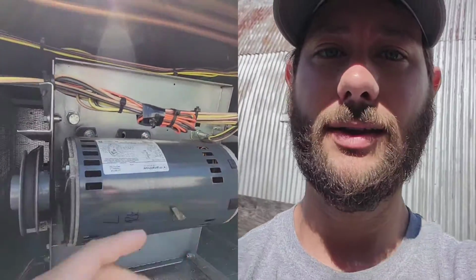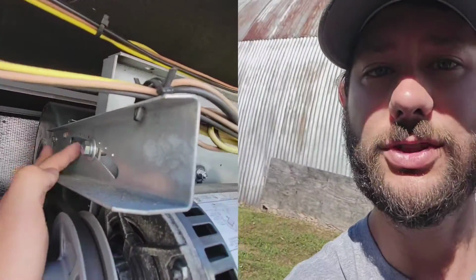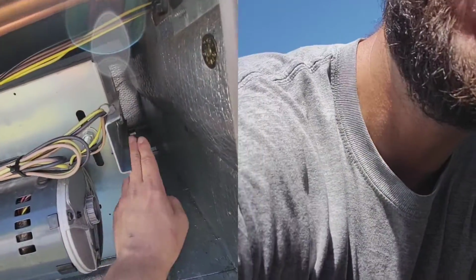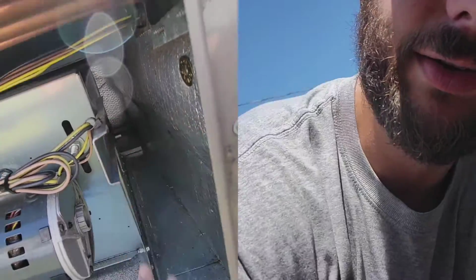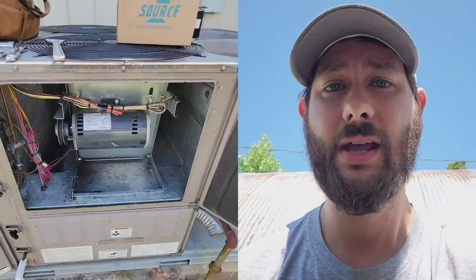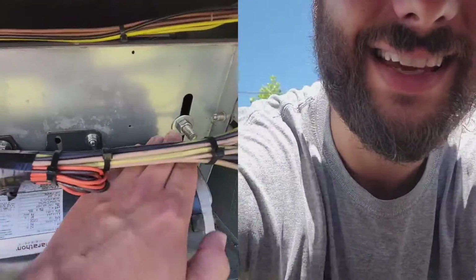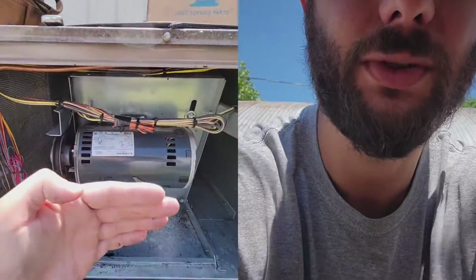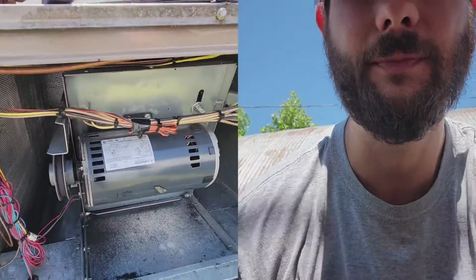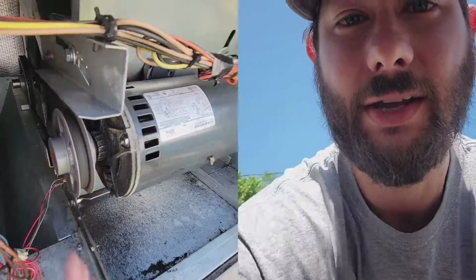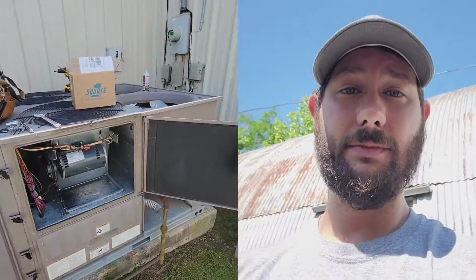But first you have to loosen this screw here, and then loosen this one here. If you don't loosen those two screws, then when you go to adjust these to pull this little mount out that the motor sits on, it's not going to increase or decrease the tension, because it's not going to be able to move.